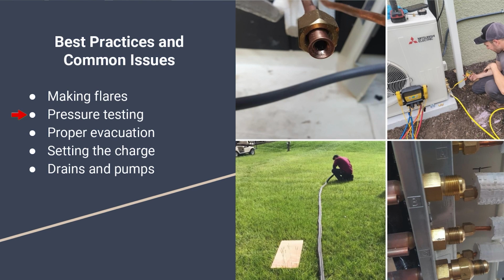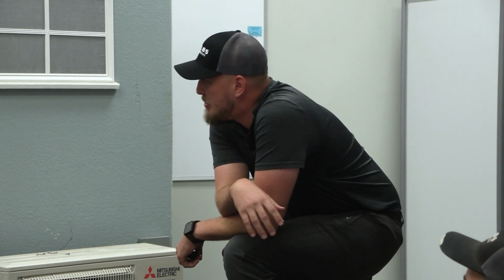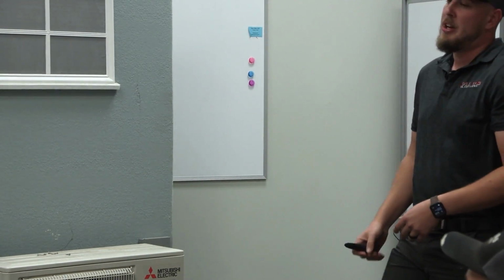Next, pressure testing. Again, refer to the manual for what pressure the manufacturer recommends. A quick rule of thumb is over 300 and under 600, but again, refer to the manual on that pressure test.